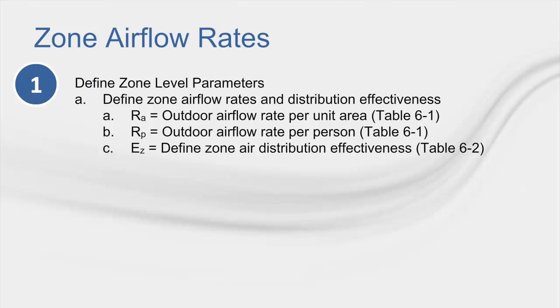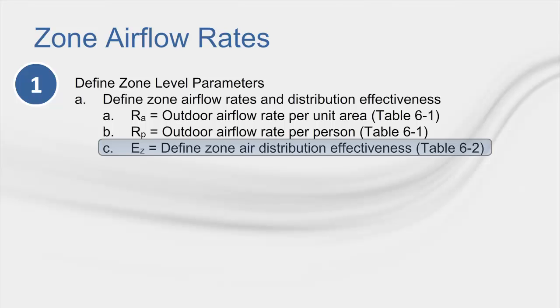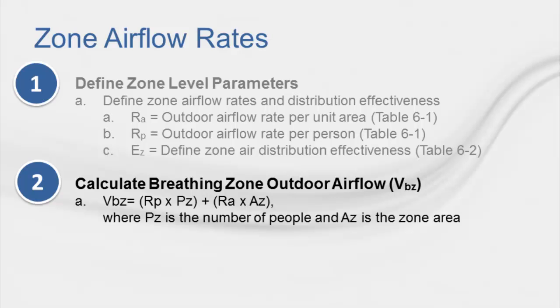The first step in the calculation is determining the zone level parameters for air flow rates and distribution effectiveness. Using Table 6-1 in the standard, you can determine R sub A, the outdoor air flow rate per unit area, and R sub P, the outdoor air flow rate per person in the zone. Additionally, Table 6-2 is used to determine the zone air distribution effectiveness. Using R sub A and R sub P from Table 6-1, you can calculate the breathing zone outdoor air flow, V sub BZ, using equation 6-1 from the standard.